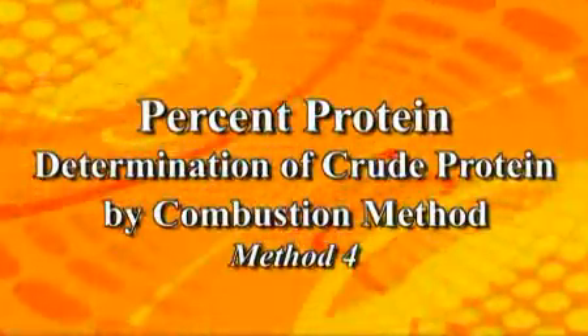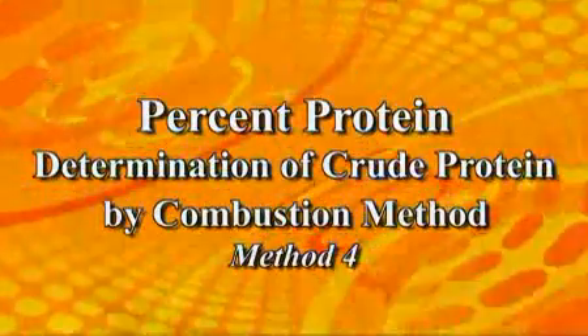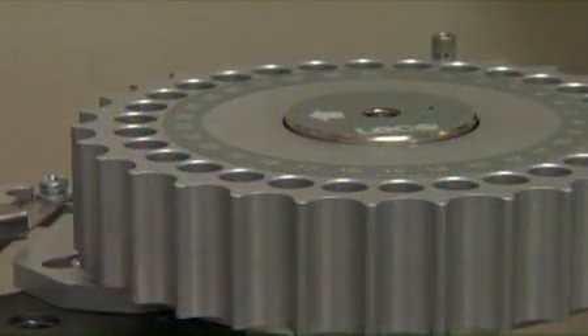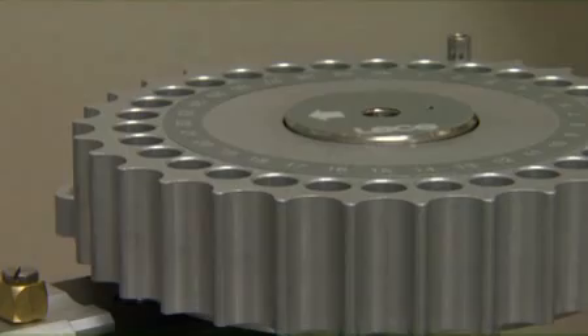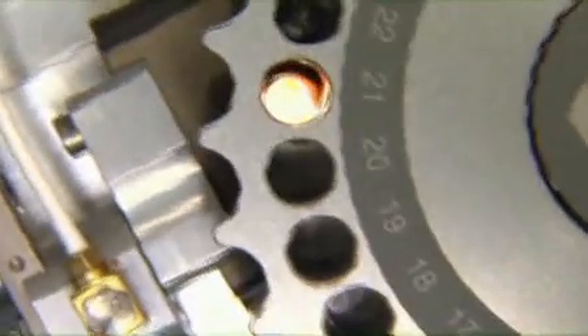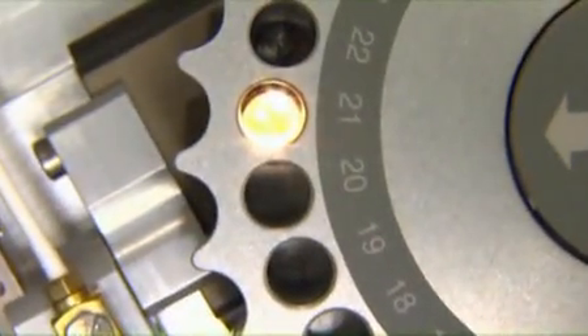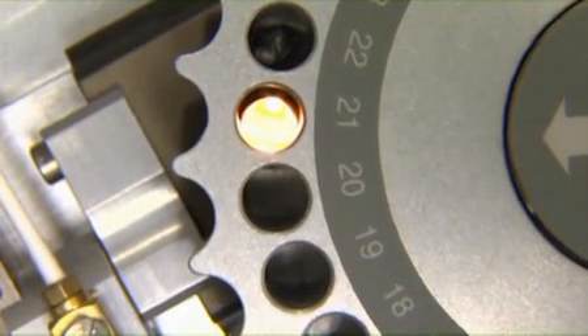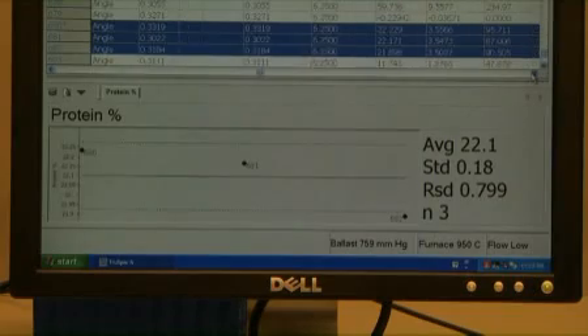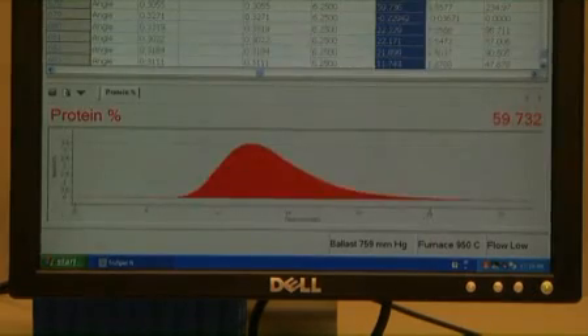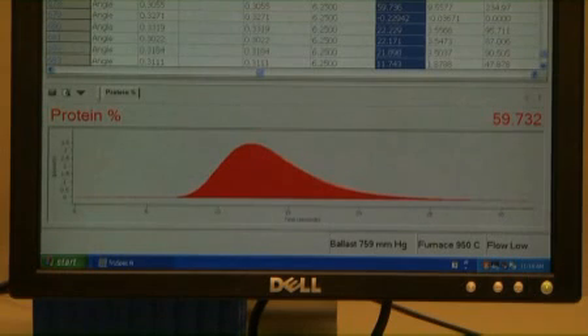This is the video presentation of percent protein, Analytical Services Method number 4. This percent protein method is a proximate analysis test based on the Dumas method, which determines the percentage of crude protein by combustion, thus freeing the nitrogen in the sample. The nitrogen is converted to crude protein by applying a mathematical factor. Keep in mind that non-protein nitrogen will also be measured.